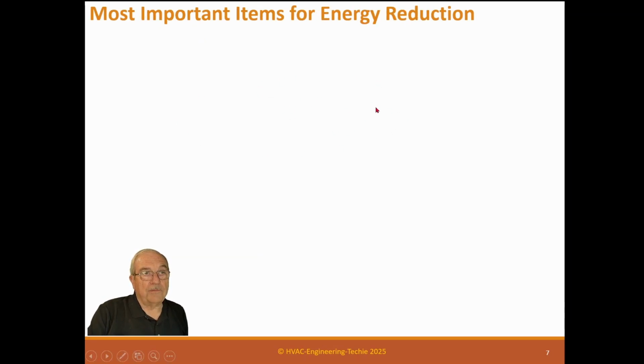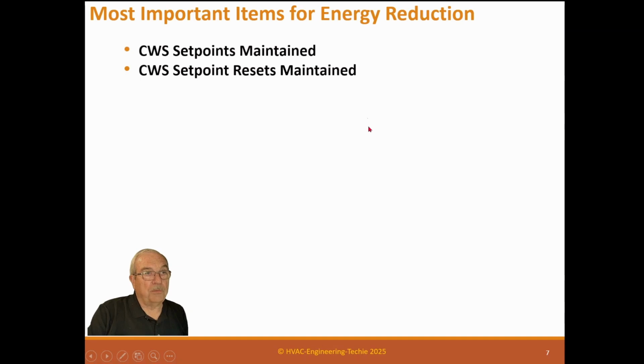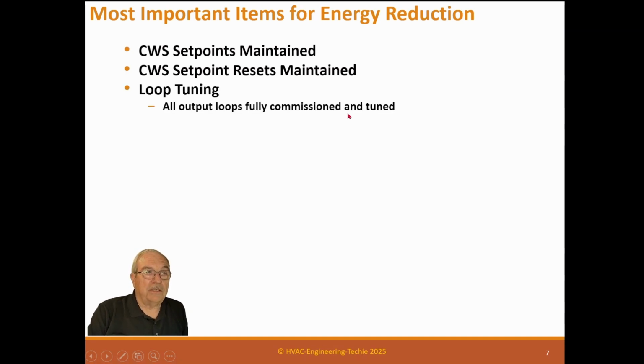Most important items for energy reduction. Condenser water set points. That's really important. Condenser water set point resets. If it's got resets, we want to maintain those resets. Loop tuning. All output loops fully commissioned and tuned. Now, that's a special process, how you tune loops. These are analog loops, of course. And we have a training session for that, of course. And the control contractor needs to tune those loops, and the commissioner needs to verify that they're tuned. And this is how we do that during our functional testing.